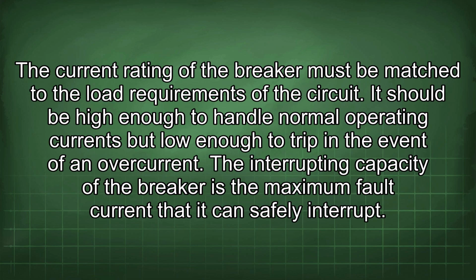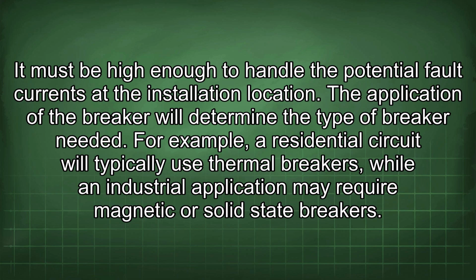It should be high enough to handle normal operating currents but low enough to trip in the event of an overcurrent. The interrupting capacity of the breaker is the maximum fault current that it can safely interrupt. It must be high enough to handle the potential fault currents at the installation location. The application of the breaker will determine the type of breaker needed. For example, a residential circuit will typically use thermal breakers, while an industrial application may require magnetic or solid-state breakers.